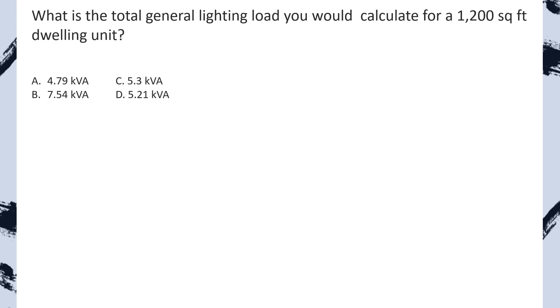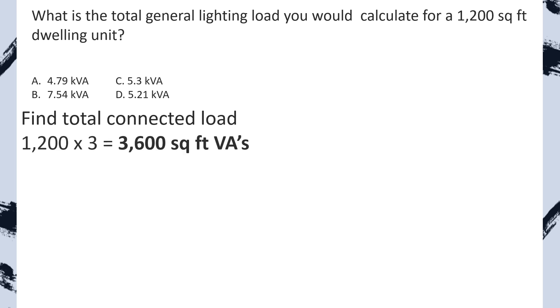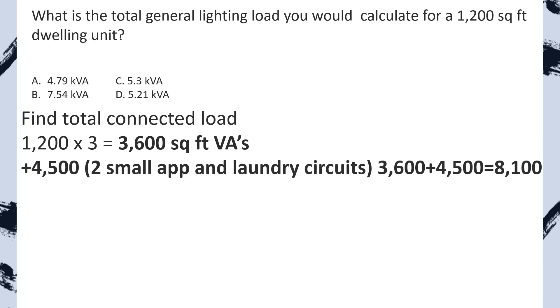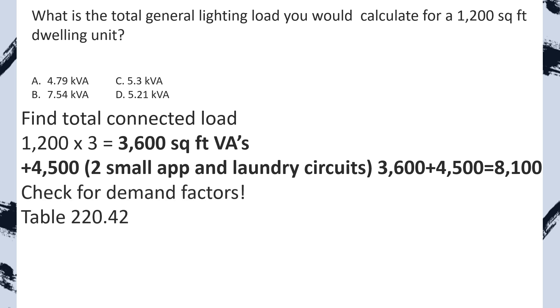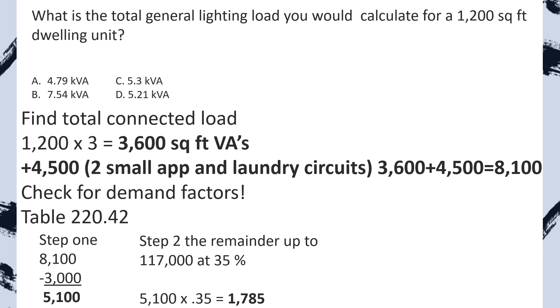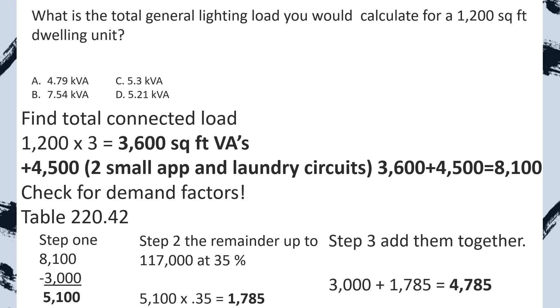What is the total general lighting load you would calculate for a 1,200 square foot dwelling unit? Anytime it asks for the total, you're always going to be applying a demand factor if there is one, and in every one of these calculations you're going to have the two small appliance and one laundry circuit. Step one: find the total connected load. We take 1,200 square feet multiplied by three VAs per square foot, which gives us 3,600 VAs. Now we tack on our 4,500 for our two small appliance and one laundry circuit: 3,600 plus 4,500 equals 8,100. Now we check for demand factors and head to table 220.42. Step one: minus 3,000 and take it at 100%. Step two: multiply the remainder by 0.35. Add them back together and we end up with a new reduced load of 4,785 VAs. We select A. Great job.